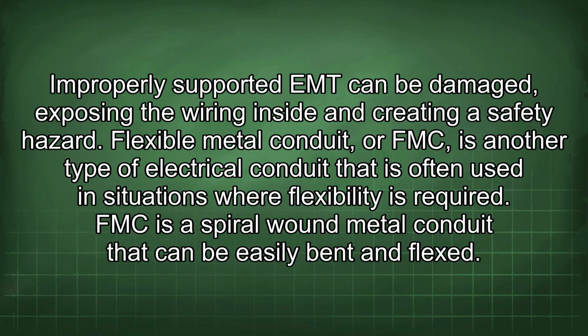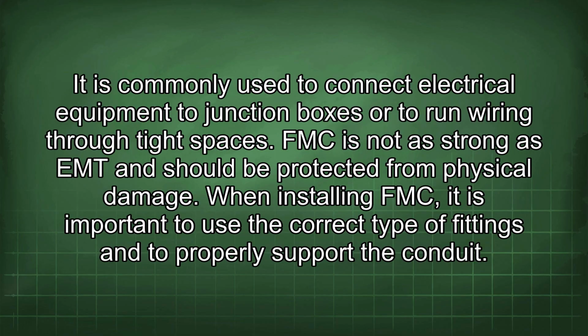Flexible metal conduit, or FMC, is another type of electrical conduit that is often used in situations where flexibility is required. FMC is a spiral wound metal conduit that can be easily bent and flexed. It is commonly used to connect electrical equipment to junction boxes or to run wiring through tight spaces. FMC is not as strong as EMT and should be protected from physical damage. When installing FMC, it is important to use the correct type of fittings and to properly support the conduit.